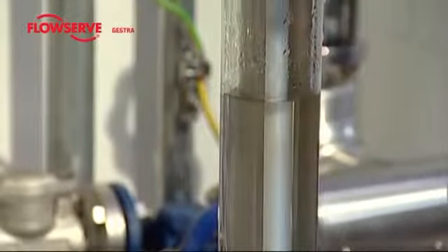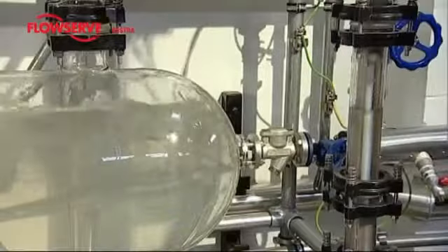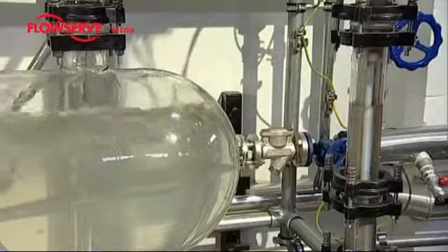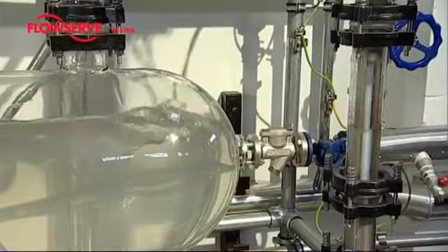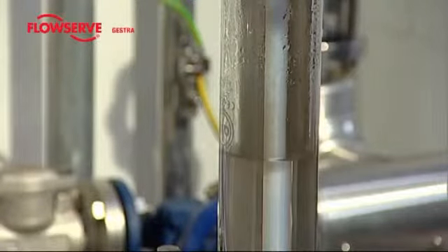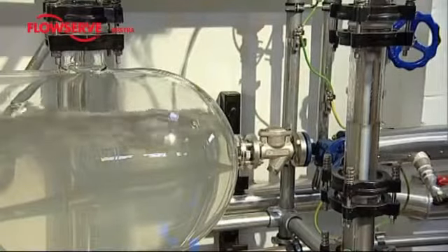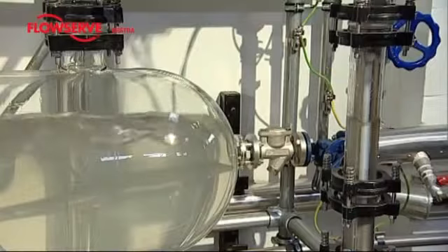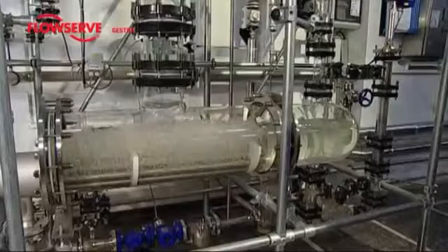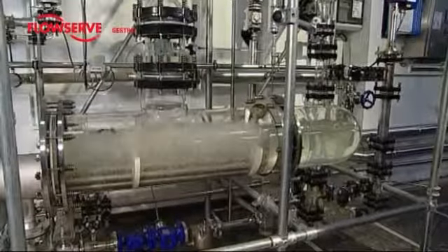Through the sinking pressure, the area loading on the individual steam bubbles in the water is reduced, so that these occupy a greater volume, lifting the water level as a result. This effect can also be observed in the external measuring pot. Indication errors cannot be excluded. When the steam outlet is closed again, the water level drops, since the quantity of steam bubbles in the water space quickly decreases again. In such a case, it's possible that the water level may drop below a preset limit, which will shut down the firing equipment.